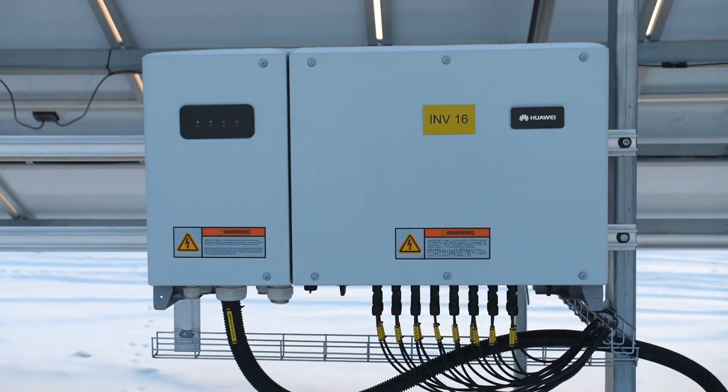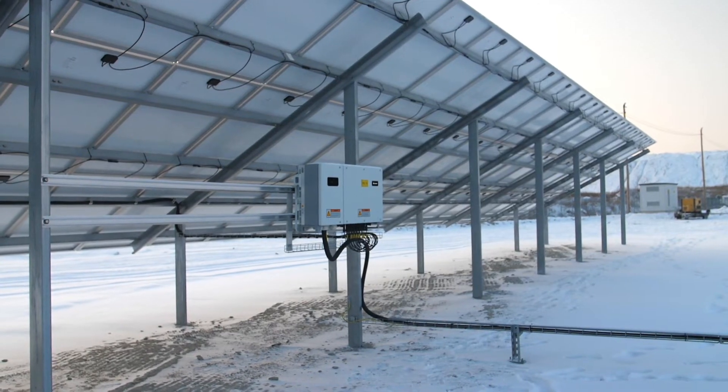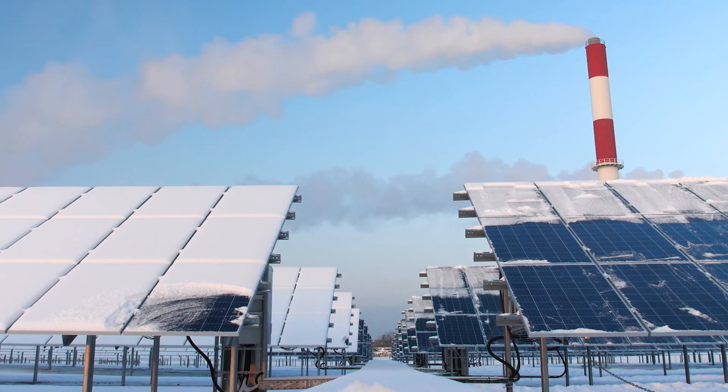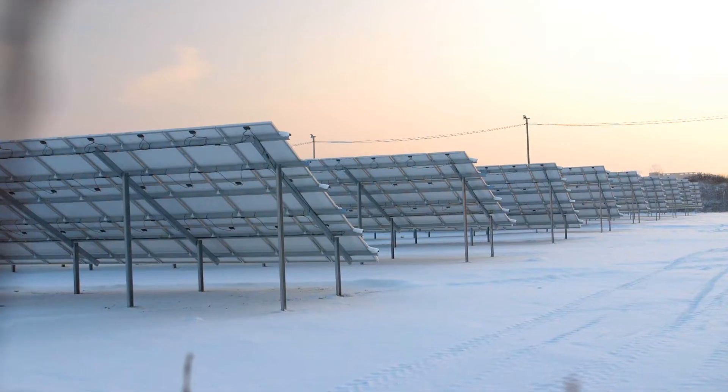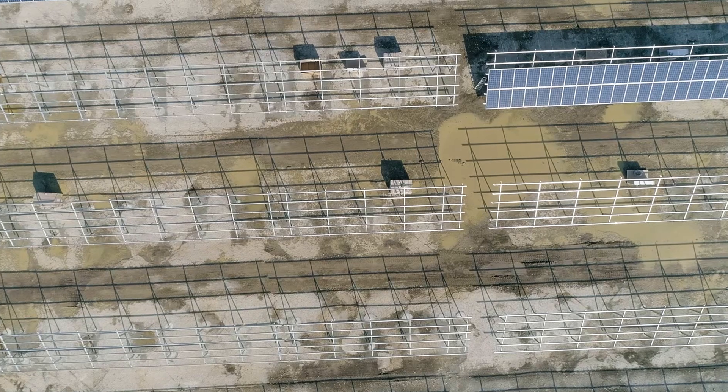There are 24 Huawei Sun 2000 series inverters with maximum output of 950 kW, and more than 4,100 SHARP PV modules with maximum peak power of 1,137 kW. The tilt of the modules is 30 degrees and expected yearly production is almost 1 gigawatt hour.